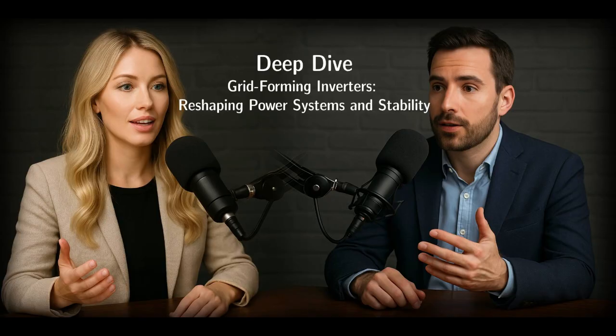Okay, the synthetic inertia is fascinating. We get traditional inertia, big spinning rotors, kinetic energy stored physically. Can you just quickly recap the practical effect of that physical inertia? How does it help the grid? Sure. Think of it like a flywheel. The kinetic energy stored, mathematically 1/2 J omega squared, resists changes in speed, which in the power system means resisting changes in frequency. The more inertia you have, represented by the system inertia constant H, the slower the frequency changes when there's a mismatch between generation and load. Buys time. Exactly. It gives operators and control systems more time to react.